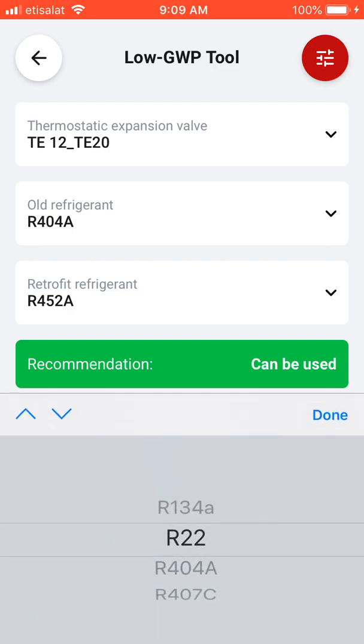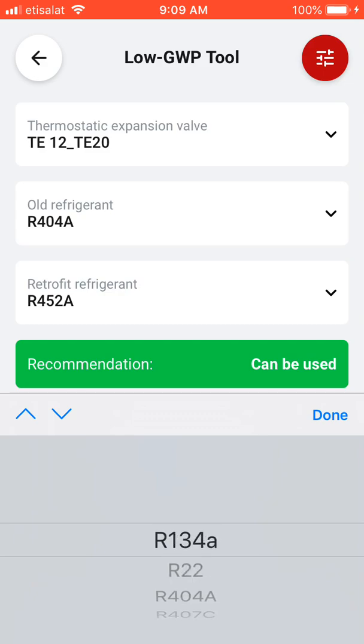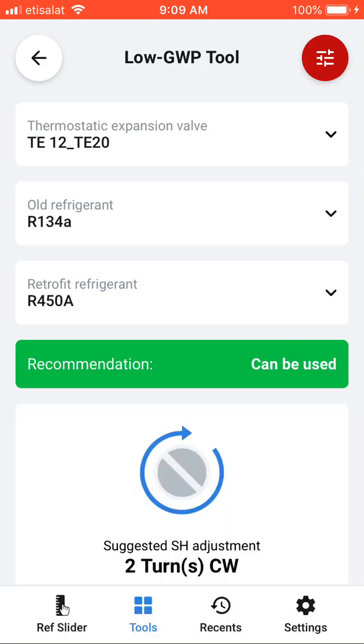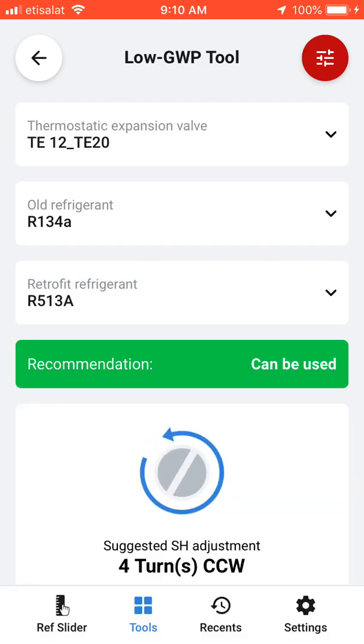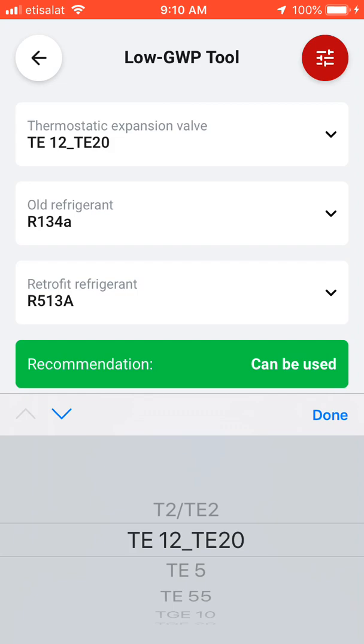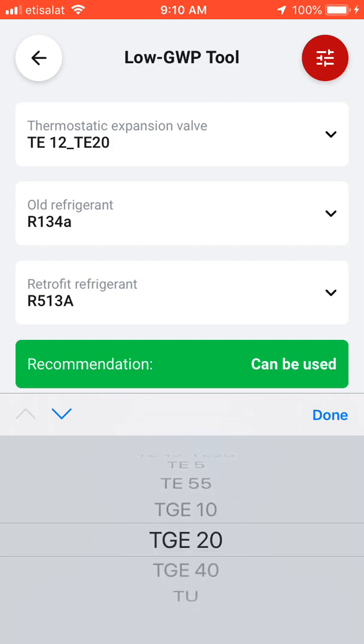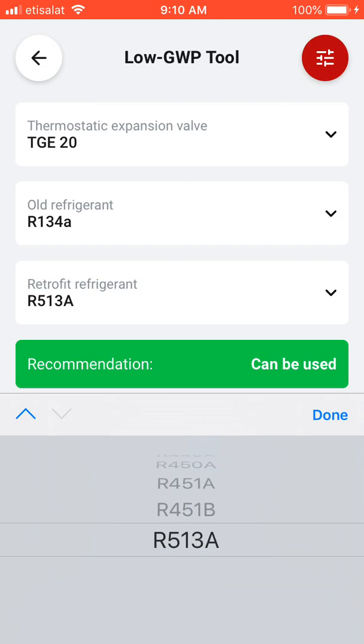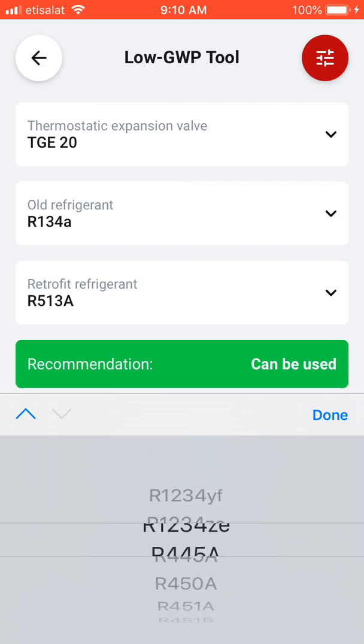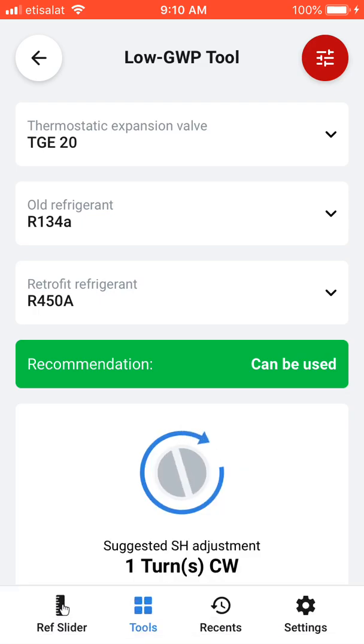If we have R134A, what can we use instead? It can be replaced with R450A or R513A. If we change the thermostatic expansion valve to a compatible type, we can still use R513A. Yes, this is a supported option.